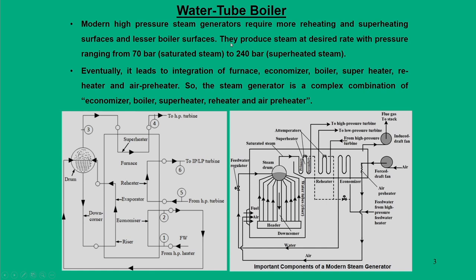Let us give a brief introduction about water tube boilers, which are nothing but modern high pressure steam generators. Normally they operate at very high pressures — 70 bar for saturated steam and 240 bar for superheated steam. Water tube boilers are nothing but the integration of furnace, economizer, boiler, superheater, reheater, and air preheaters — in other words a complex combination of all these components.